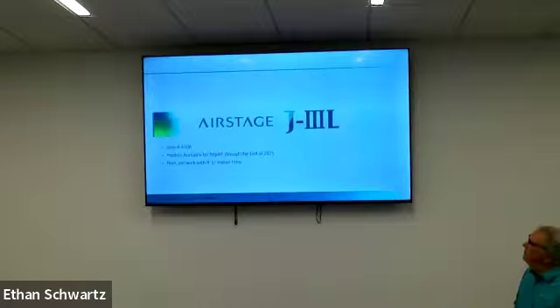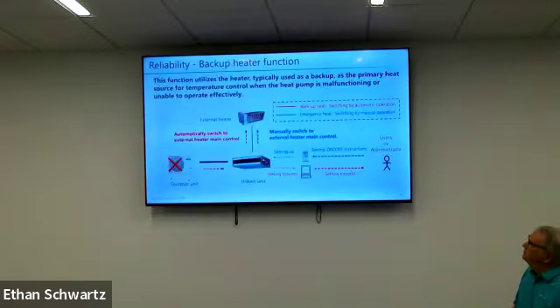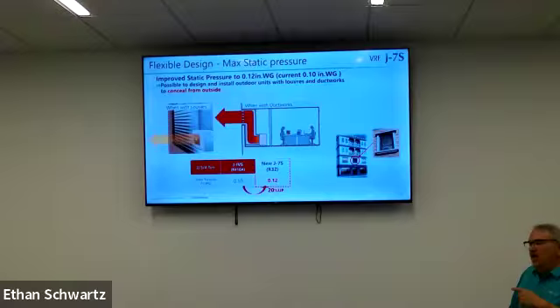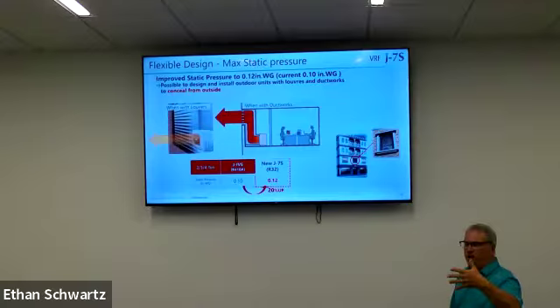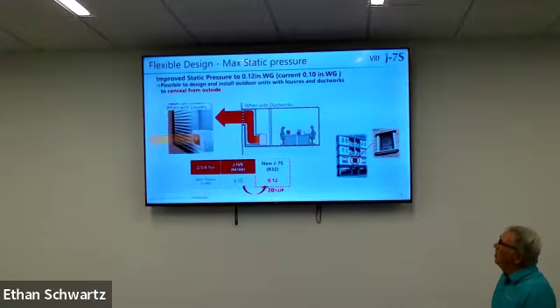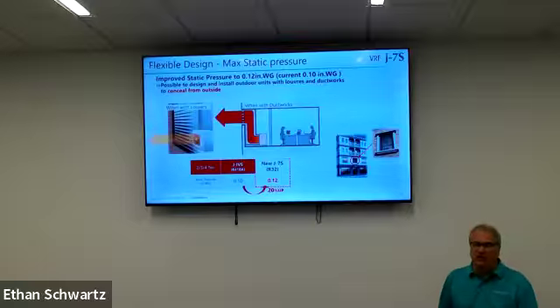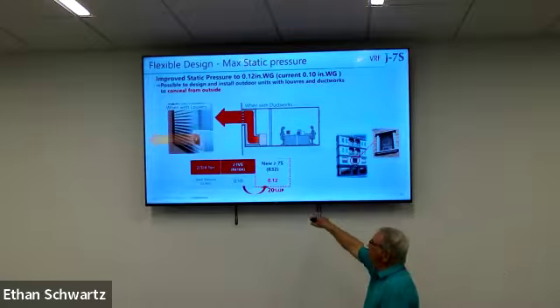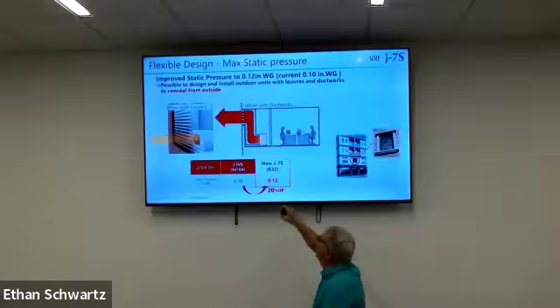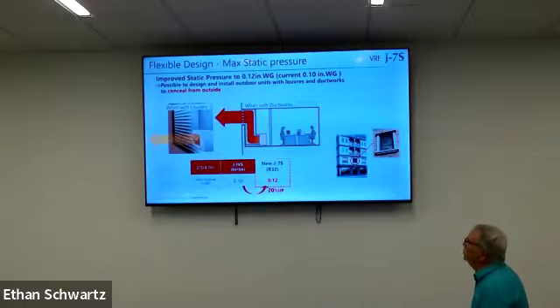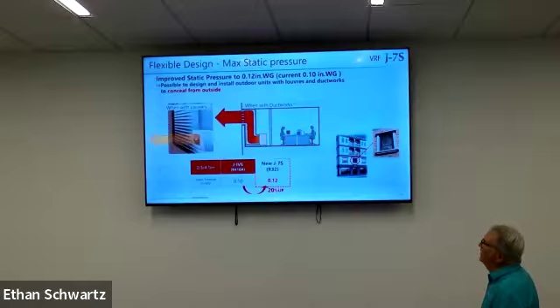The other thing, well, way too much. The other thing is that I didn't point it out, but on that example building, you kind of saw where the 3 units looked like they were inside the building. Yeah, that's because on our J7S, actually all of our VRF equipment, we can attach ductwork to the face of it, set a function code telling it that we can have some amount of ductwork on the front of that unit and put those units inside.